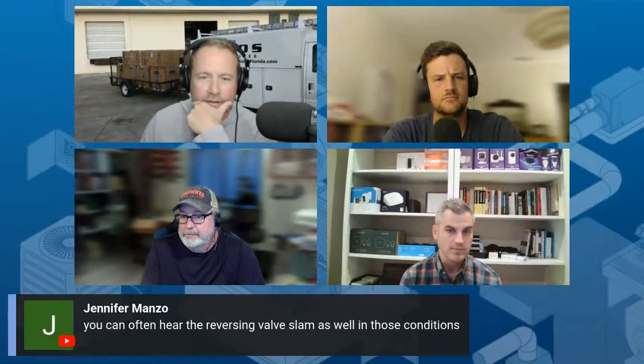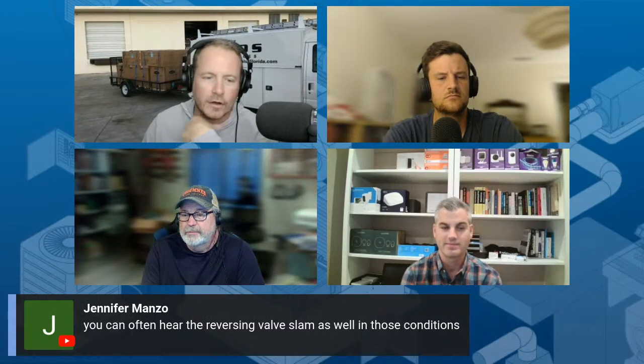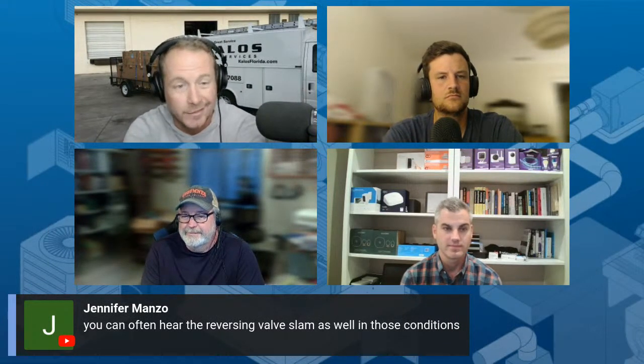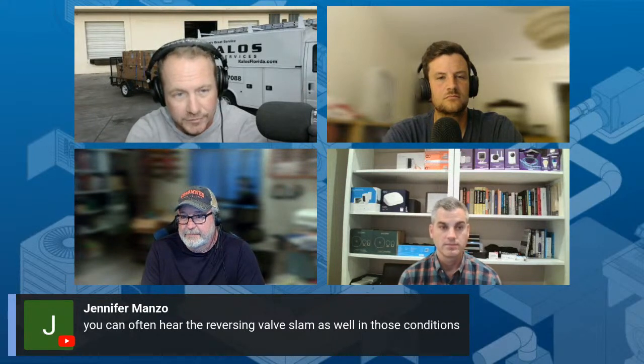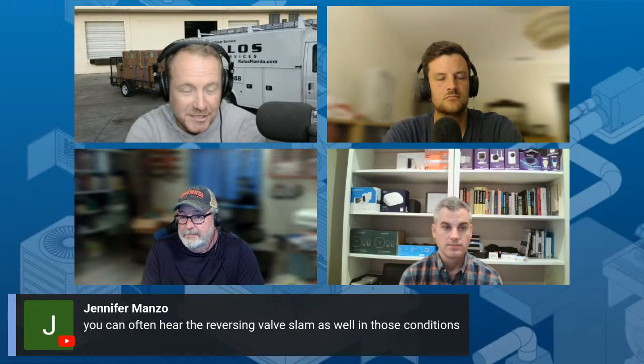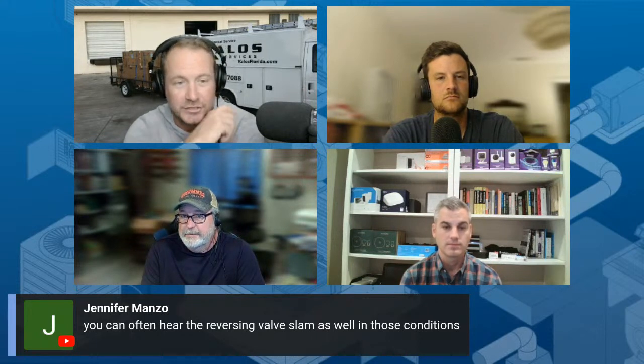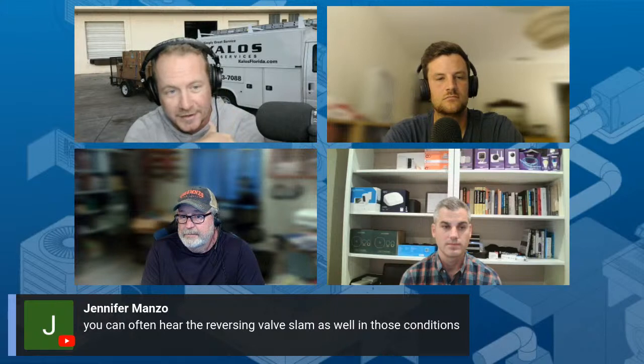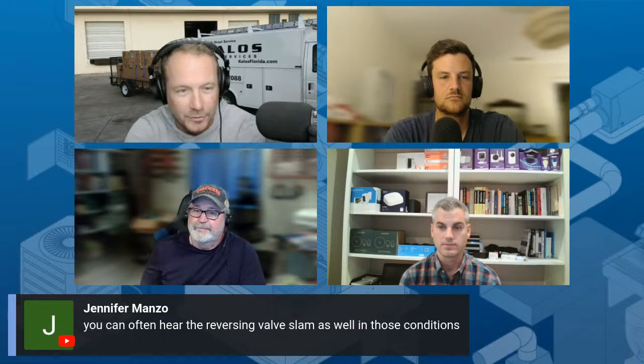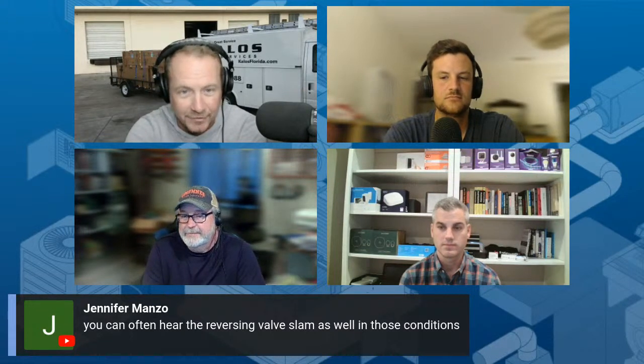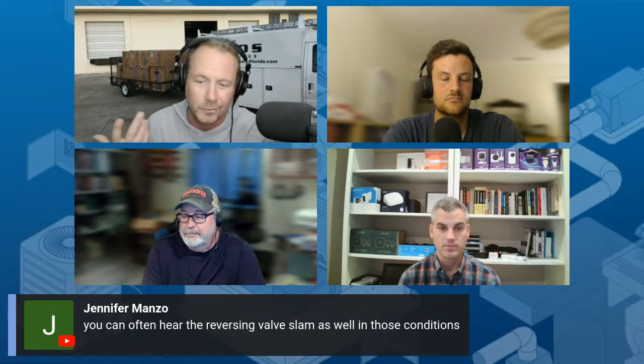I want to get to a couple of these questions or statements. Jennifer also said you can often hear the reversing valve slam. A lot of manufacturers do allow for a quiet shift mode, but there is an expense there, where you have a time delay. Basically, it shuts off and allows it to equalize a little bit, then it shifts. So in order to not have Mrs. Johnson call you about the crazy noise, you see a little bit of a capacity decrease. But especially where that condenser is going to be heard, outside of a window or something like that, that's a really good mode to deploy where you have that option.